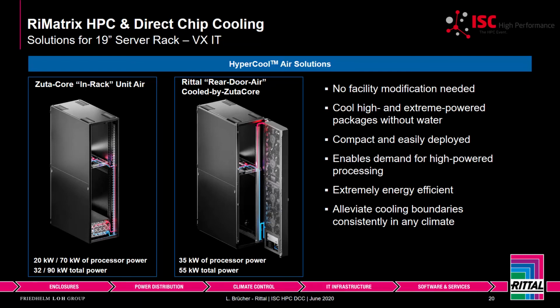So these here are our two solutions we're offering. First, the in-rack solution on the left side of the screen. It's a 6U solution that can cool up to 20 kilowatts of processing power or 32 kilowatts total power. It's an air-cooled solution, so the incoming air into the unit is cooling the Novec, and the Novec in itself is then cooling the processors via pipes. We're also working on an expansion of this unit to make it water cooled, which will allow cooling up to 70 kilowatts of processor power or 90 kilowatts total power.